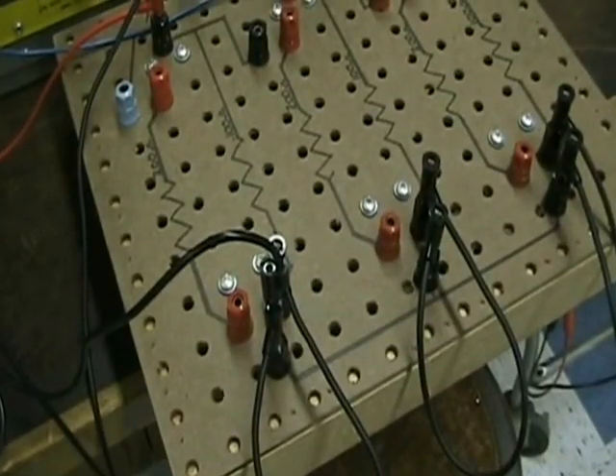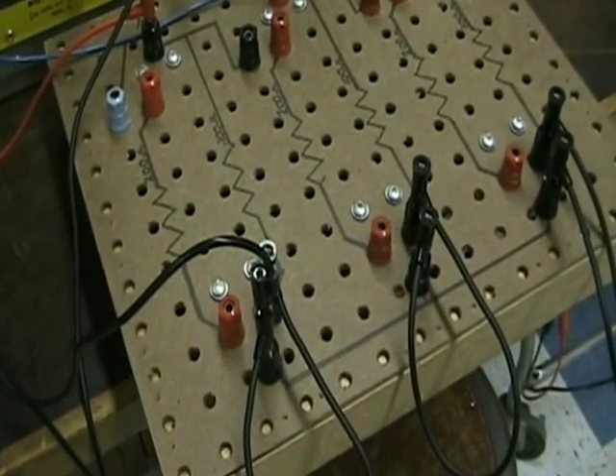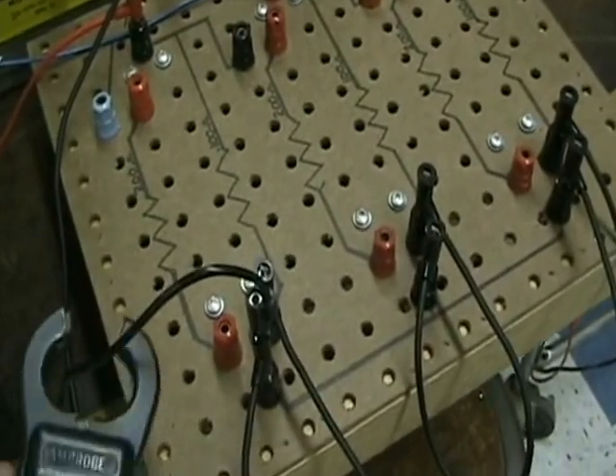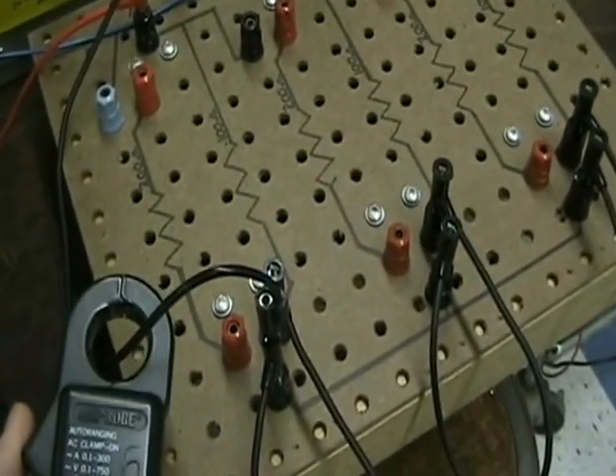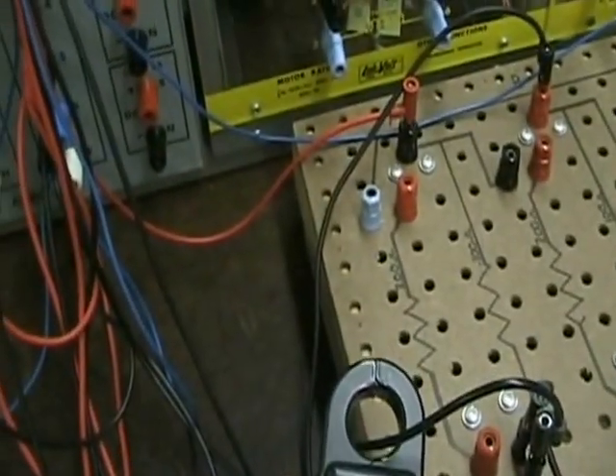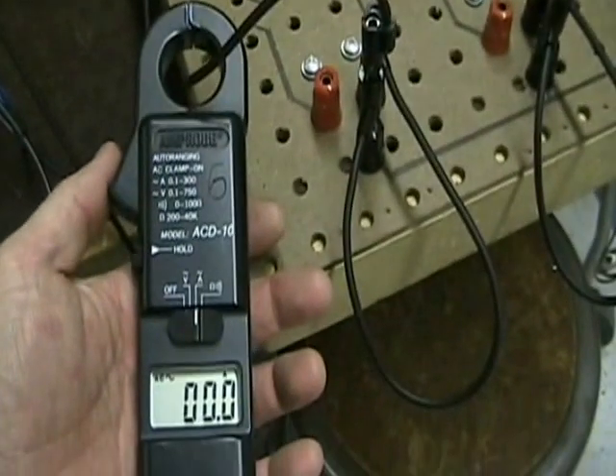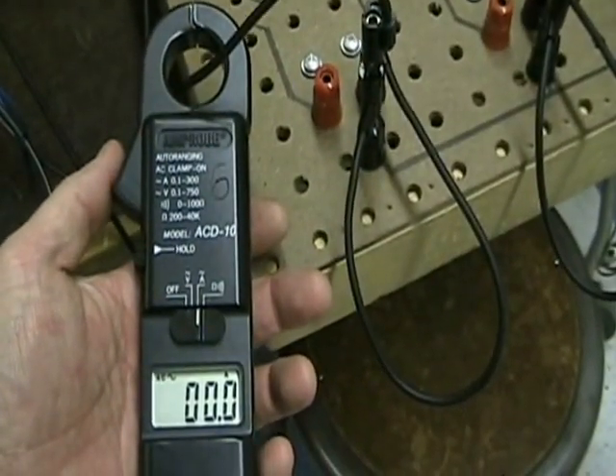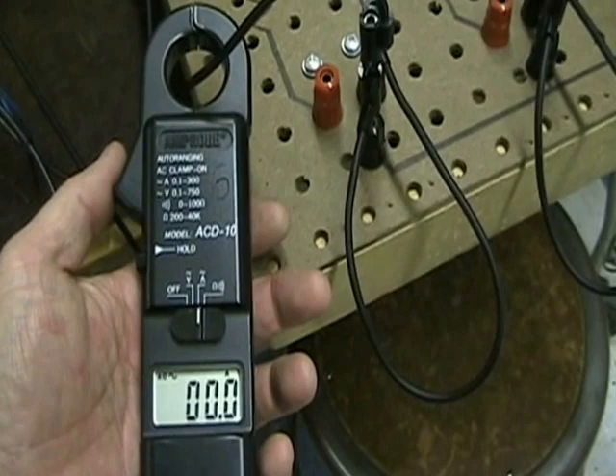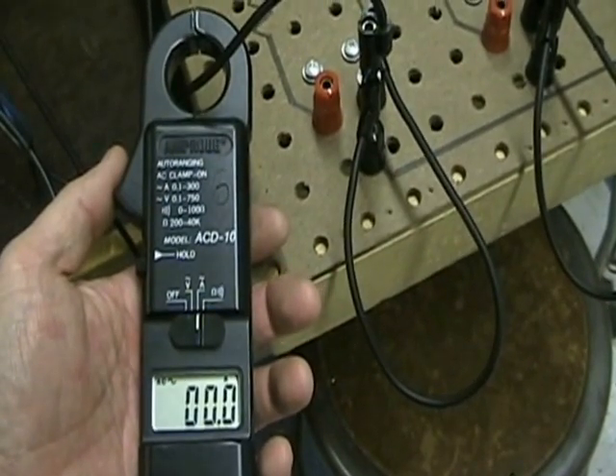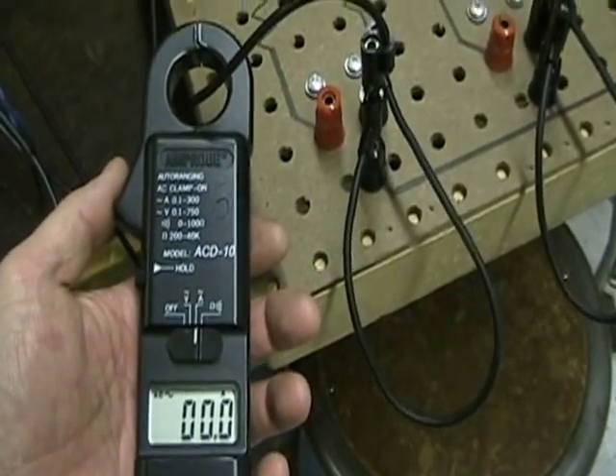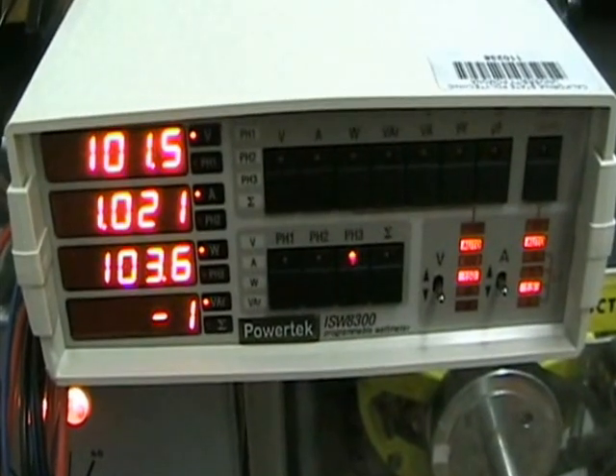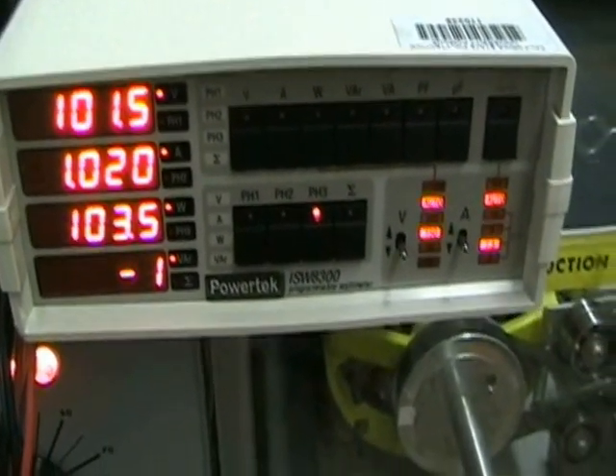The last quantity to measure is the neutral current, which is from the common point of the load to the neutral on the unit. In this case of a balanced load, the neutral current is zero or very near zero in most cases since the three phase currents are almost identical.